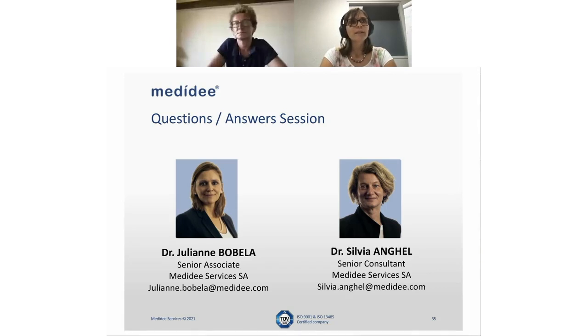Now, PMPF activities can be all sorts of activities. They don't need to be really a clinical performance study. It can be a different type of follow-up of clinical performance, but you need to duly justify if you don't perform such activities. And then whether or not it's going to be a clinical performance study or not will depend really on the clinical data that you have already available, and if there is a need to further assess certain aspects of your device once placed on the market.